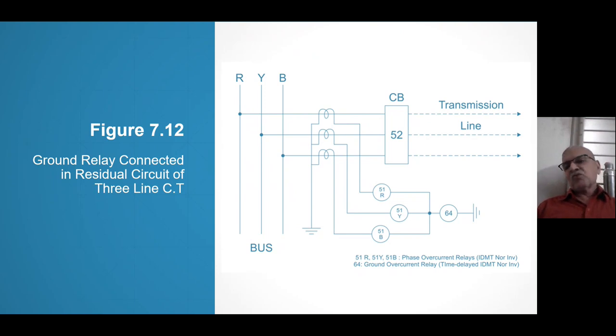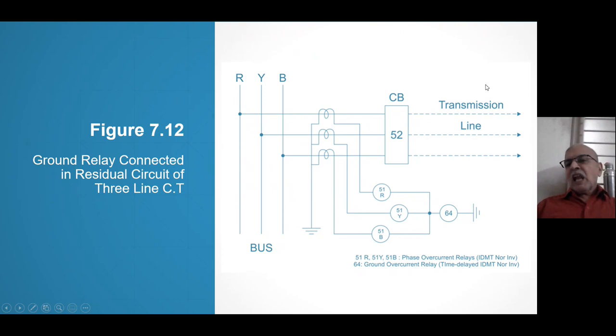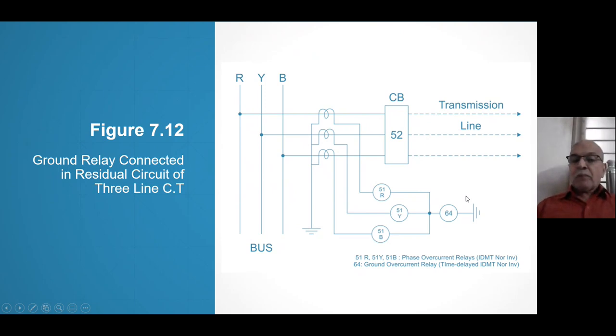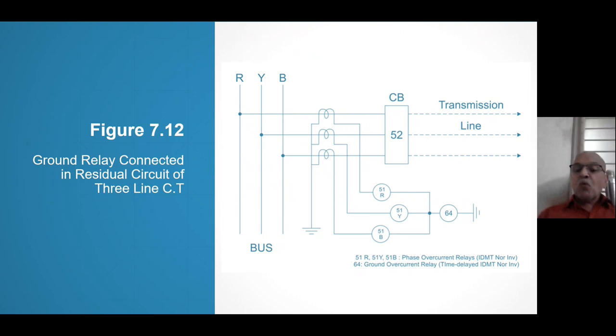Not only that, but the relay will not operate for a triple-line fault either. If due to fault 900 amperes pass, then on the 100/1 CT secondary that is 9 A, and 9 + 9 + 9 is also zero because it is a symmetrical fault. So relay 64 will not — and must not — operate, because the relay should indicate which kind of fault has occurred.